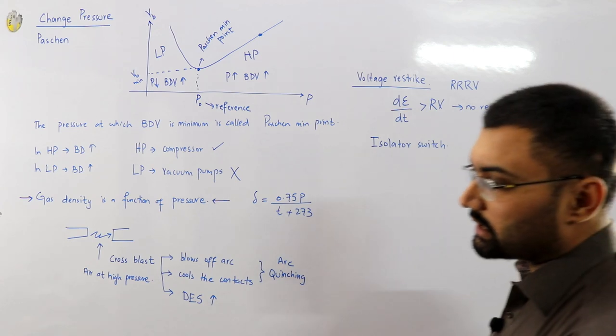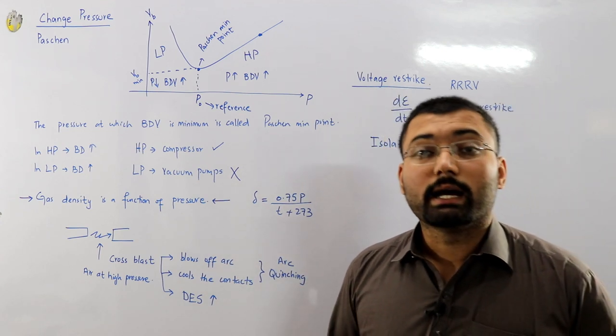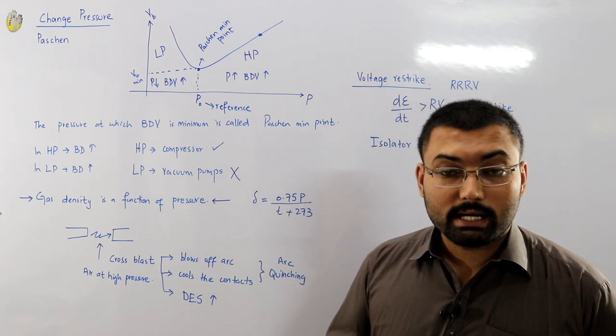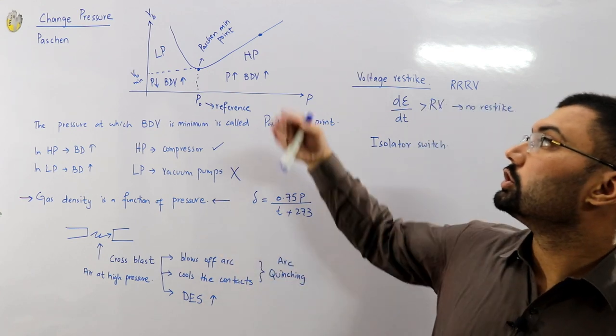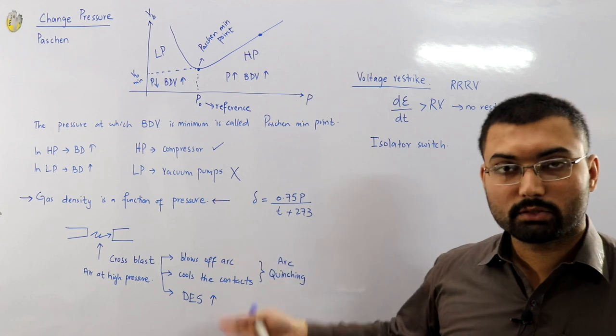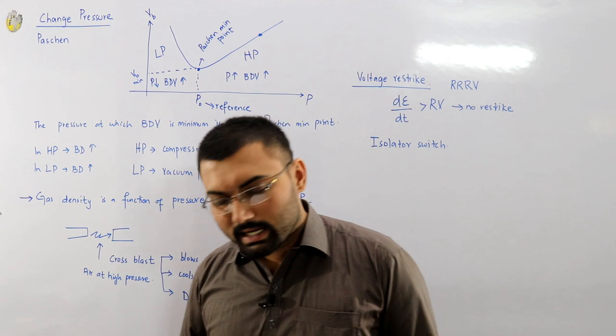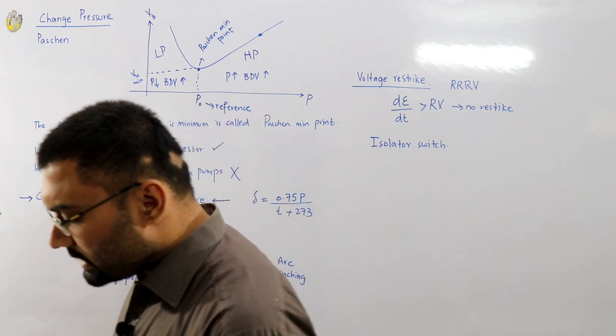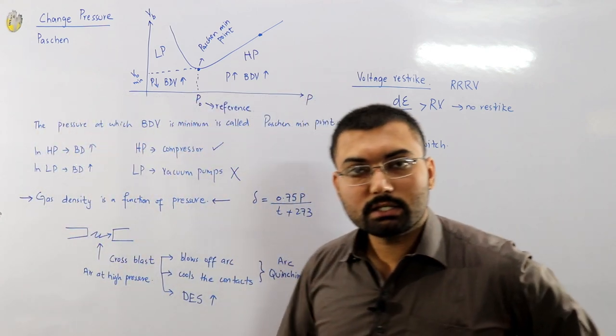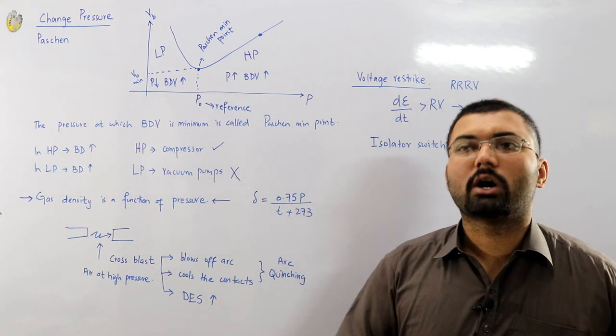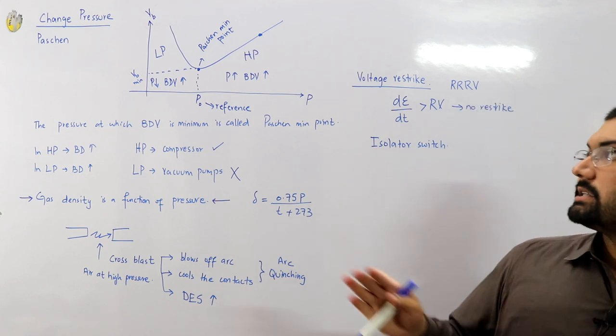We also have the SF6 circuit breaker. SF6 has a high dielectric strength, acts as a coolant as well, and if you increase or decrease the pressure the dielectric strength further increases. Similarly, we have vacuum circuit breakers — on the low density side — and liquid oil circuit breakers as well, which we may see in the liquid dielectrics section.